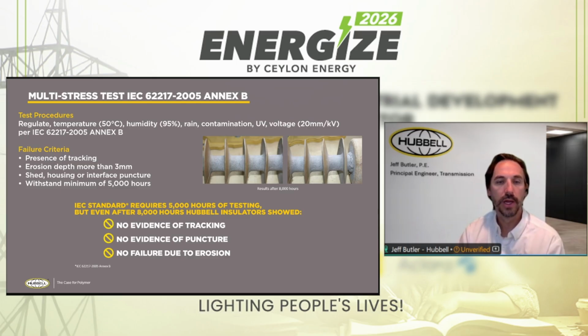The test per the standard does define 5,000 hours, but we actually increased that and ran the test for 8,000 hours. So the photos that are shown there are the insulators after 8,000 hours. That is 60% more exposure in the test, and yet we still successfully passed the test. Now, unlike the UV test, we can't equate this to a real-world lifespan of the insulator, but it does represent that even after a significant amount of exposure to a very challenging environment, the insulator still performed very well.